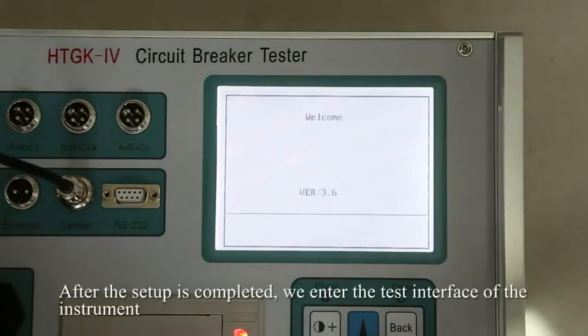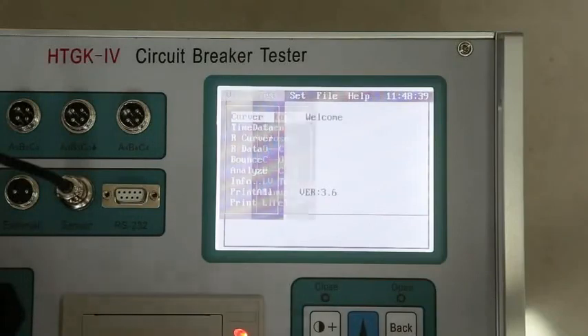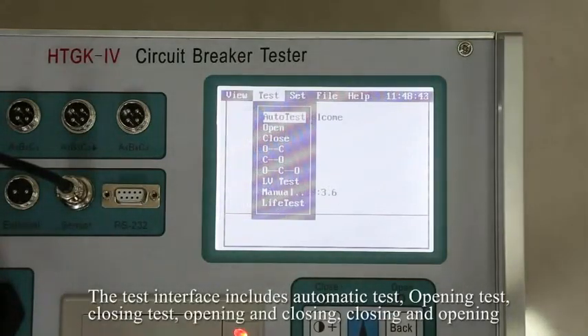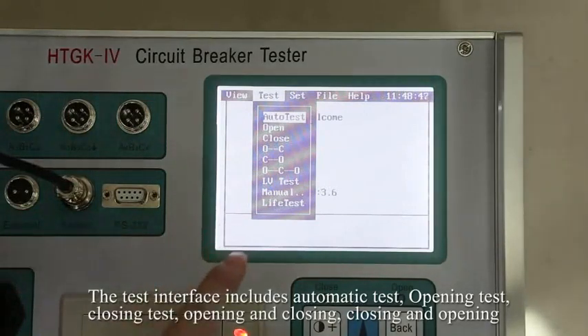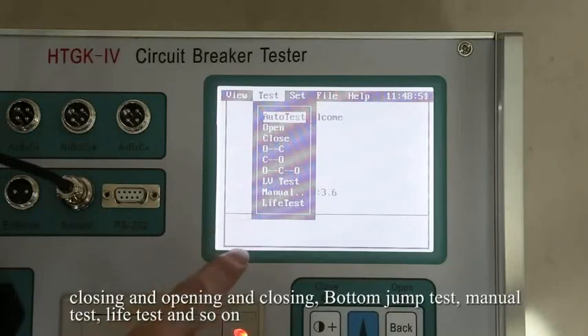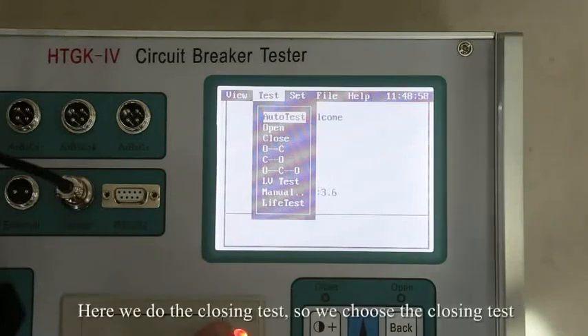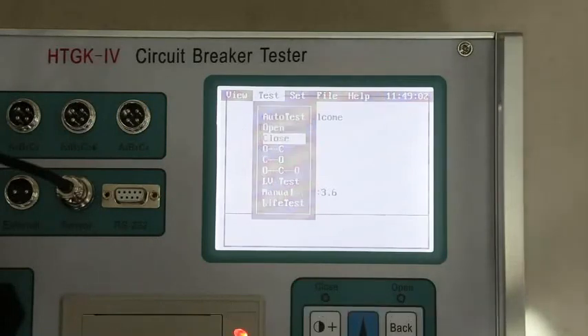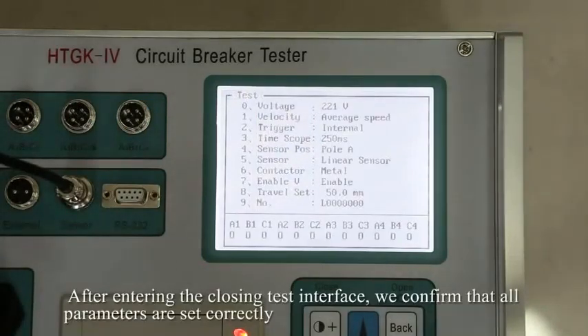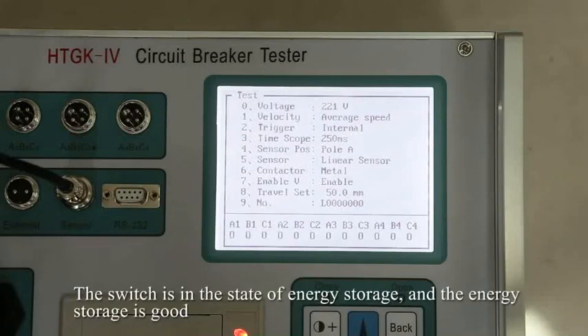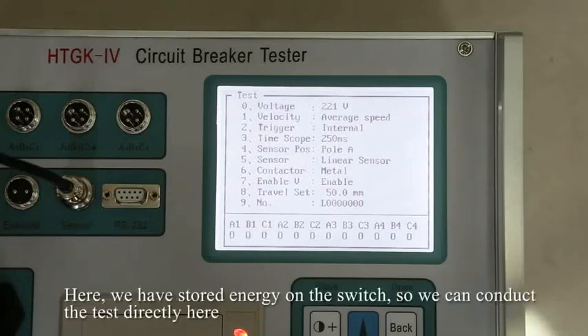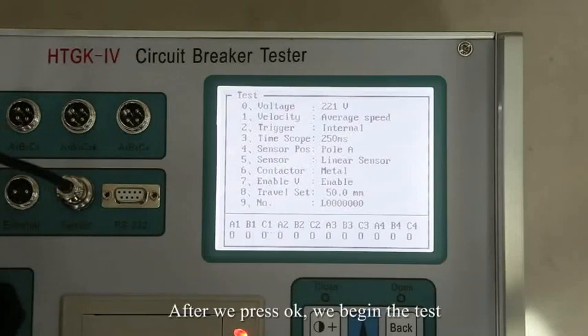After the setup is completed, we enter the test interface of the instrument. The test interface includes automatic test, opening test, closing test, opening and closing, closing and opening, closing and opening and closing, button jump test, manual test, life test, and so on. Here we do the closing test, so we choose the closing test. After entering the closing test interface, we confirm that all parameters are set correctly. The switch is in the state of energy storage, and the energy storage is good. Here we have stored energy on the switch, so we can conduct the test directly. After we press OK, we begin the test.